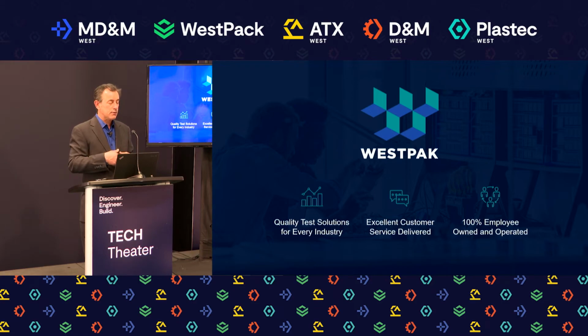And then also, if you have accelerated aging data, you've already increased that temperature. So there isn't any real need, because you've already shown that the temperature you accelerated aged at has exceeded, typically, your upper limit storage temperature. So you've already done it for 46 days or whatever. I would leverage something like that to say, no, I don't need to store it at the upper limit.